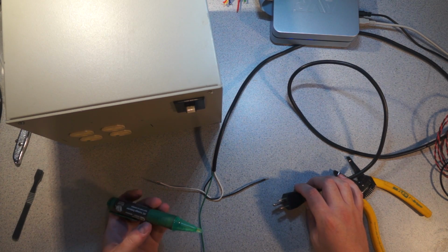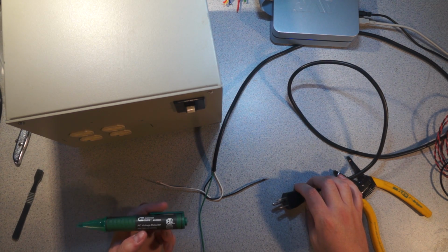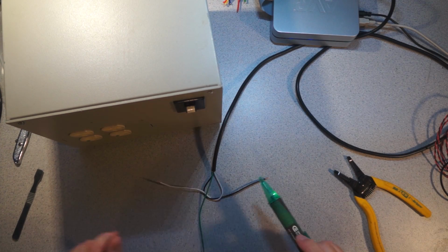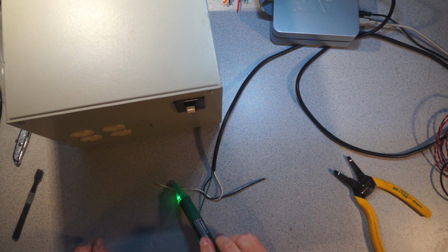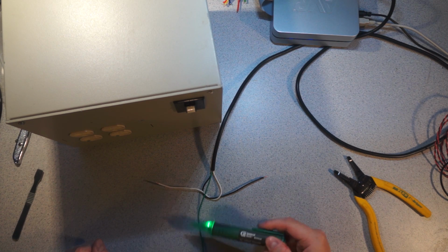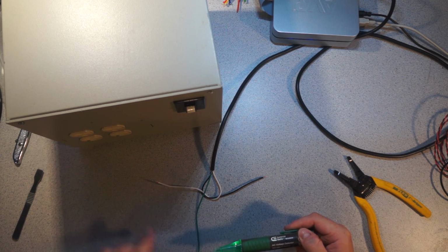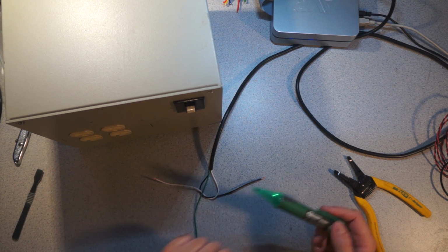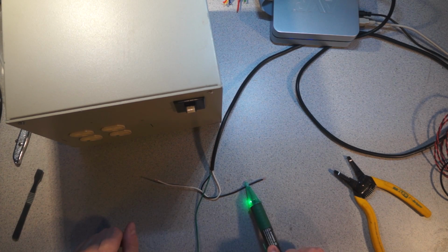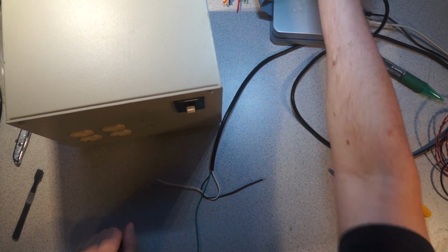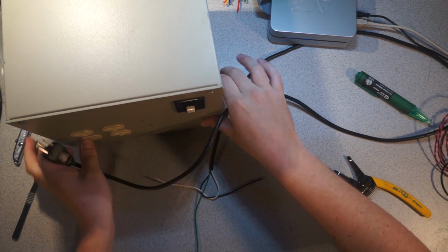Here I have a rather low quality AC voltage detector. So if we just plug this in right now, we can see that black is hot, there's nothing on white, and there's nothing on green, which means I can touch either of these without any trouble, but I'd get a nice tingle if I touched that. Rather annoying voltage detector. So what I can do is plug this into the isolation transformer.